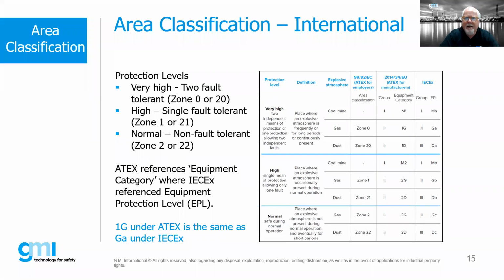So again, a very high protection level would be very high fault tolerant. And again, under the ATEX directive, it references equipment categories, where under the IEC Ex, it references equipment protection levels. So categories and equipment protection levels basically mean the same thing. So when we talk about a 1G environment under ATEX, under IEC Ex, this would be considered to be a GA. If we talk about 2G under the ATEX directive, that's equivalent to IEC Ex GB. And then finally 3G, that would be equivalent for GC applications.